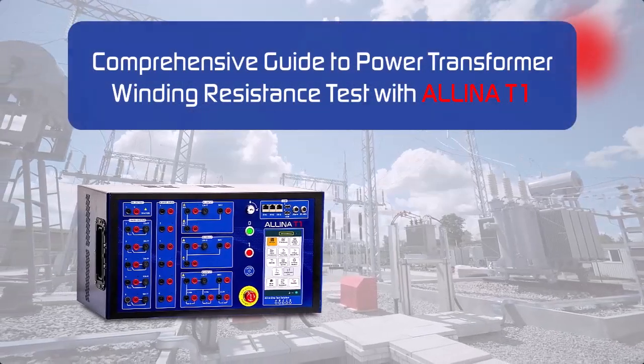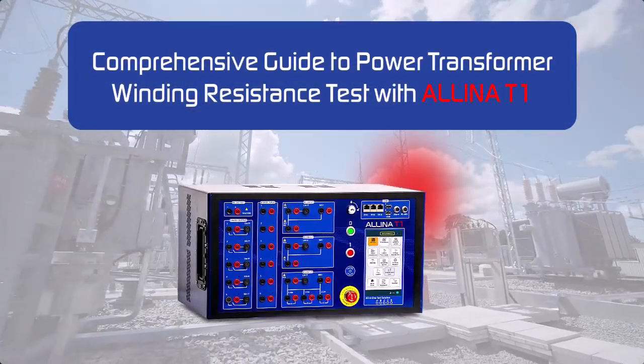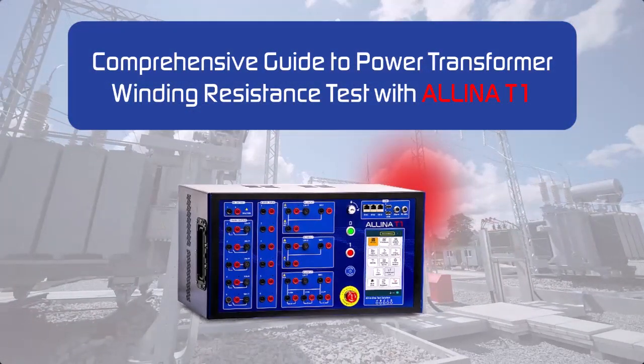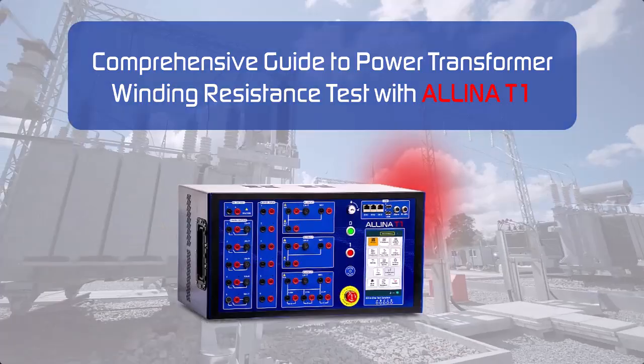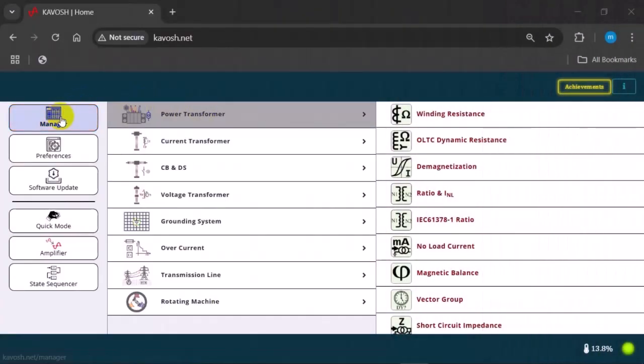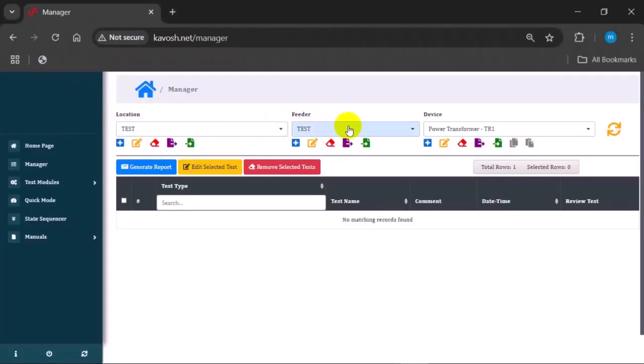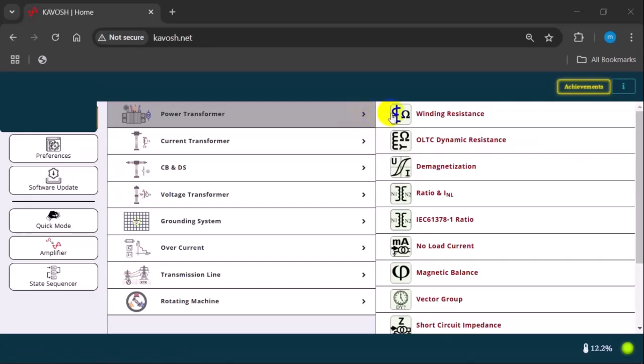In this video, we'll show you how to perform a winding resistance test on a power transformer using the ALLINA T1. After powering on the device and entering the required power transformer details through the Manager section, we proceed to set up the test parameters. For this, navigate to the Power Transformer Test menu and select the Winding Resistance Test option.